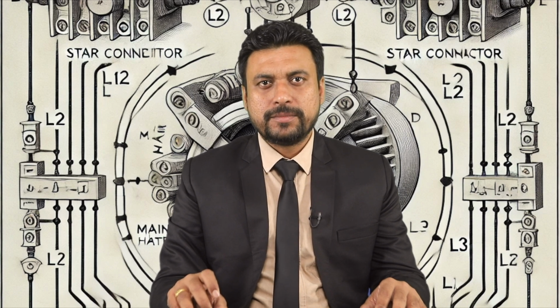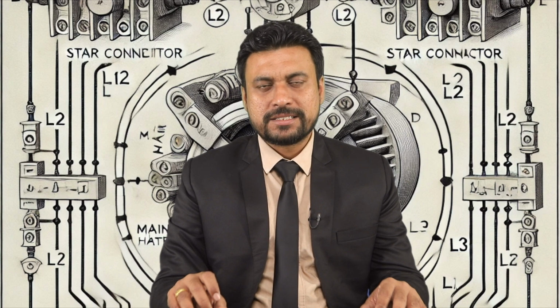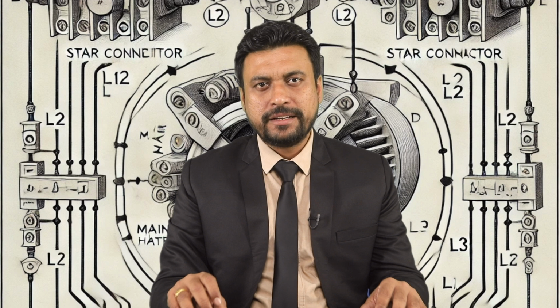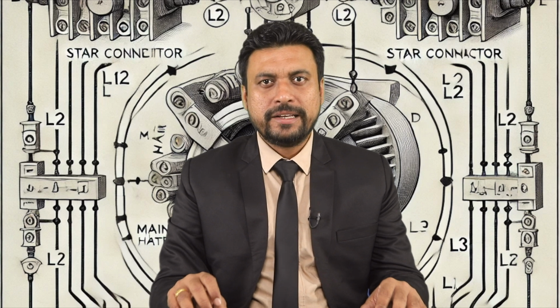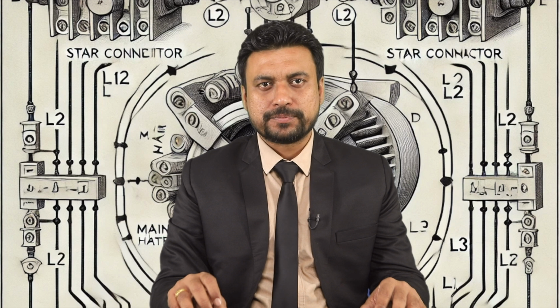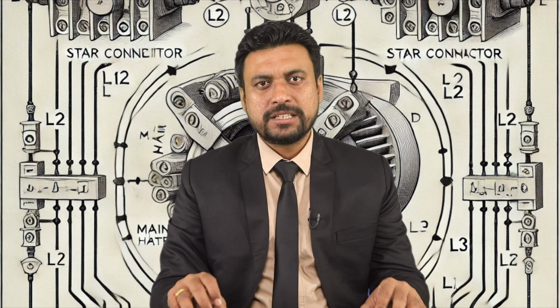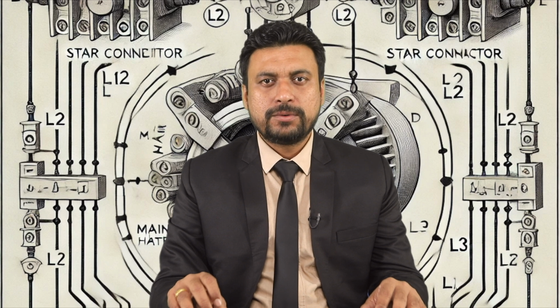This is beneficial because it reduces the mechanical stress on both the motor and the machinery it drives, leading to a smoother and less stressful start. The star connection allows the motor to gradually accelerate without the high initial torque that could potentially damage the mechanical components.